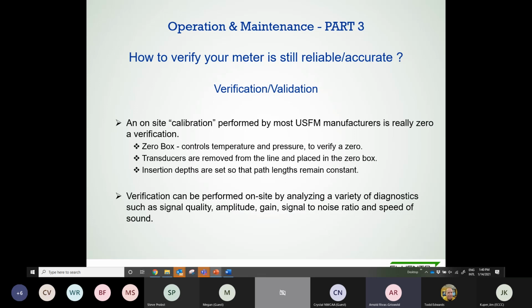If there's any drift over time, you can easily offset that, as long as the meter or the sensors are still healthy and the signals are strong enough. So that's what we do. And then we can do a variety of diagnostics involving the signal quality. We see the amplitude gain, signal to noise ratio, and the speed of sound, like I mentioned before. So those are the kind of things we do.